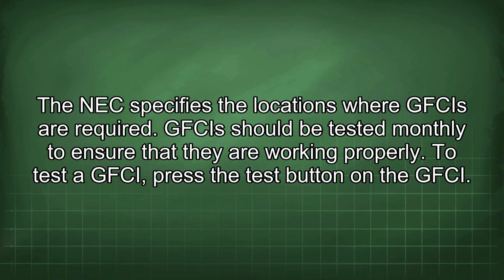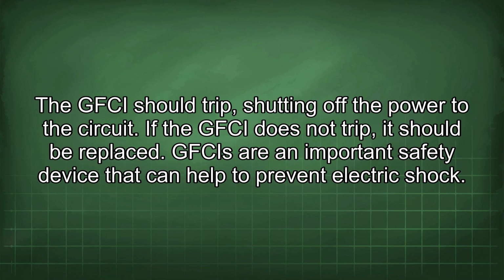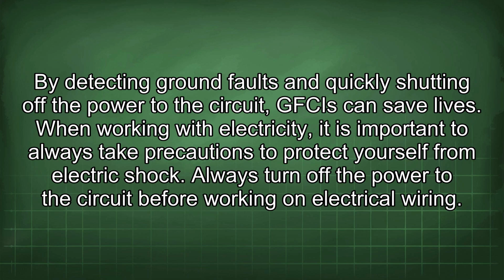GFCIs should be tested monthly to ensure that they are working properly. To test a GFCI, press the test button on the GFCI. The GFCI should trip, shutting off the power to the circuit. If the GFCI does not trip, it should be replaced. GFCIs are an important safety device that can help to prevent electric shock. By detecting ground faults and quickly shutting off the power to the circuit, GFCIs can save lives.